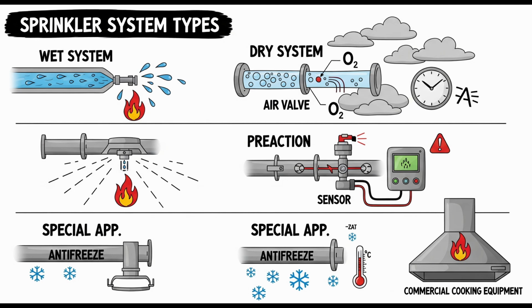Correct. Now, dealing with cold is a major theme here. Even for wet systems, there's a rule about preventing freezing near valves. There is, and it's very specific. You cannot use electric heat tracing cable wrapped around the pipe or valve instead of providing a permanently heated valve enclosure. So no wrapping it in heat tape like you might on a water pipe at home. Right. Not for these critical valves. You need a little heated room or cabinet for the valve. A dedicated heated space. Exactly.